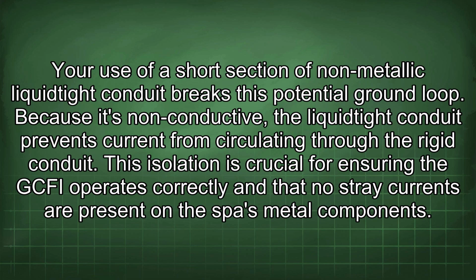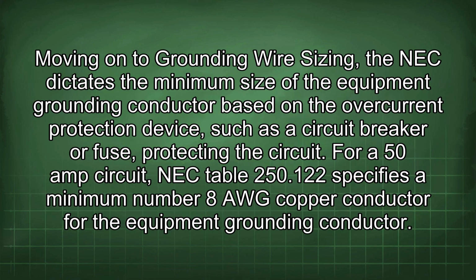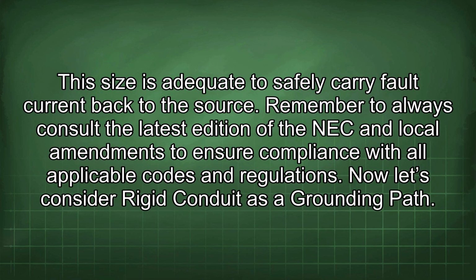Moving on to grounding wire sizing, the NEC dictates the minimum size of the equipment grounding conductor based on the overcurrent protection device, such as a circuit breaker or fuse protecting the circuit. For a 50 amp circuit, NEC Table 250.122 specifies a minimum number 8 AWG copper conductor for the equipment grounding conductor. This size is adequate to safely carry fault current back to the source. Remember to always consult the latest edition of the NEC and local amendments to ensure compliance with all applicable codes and regulations.